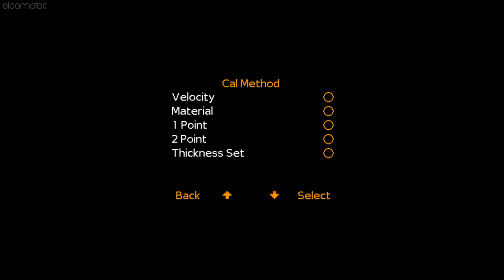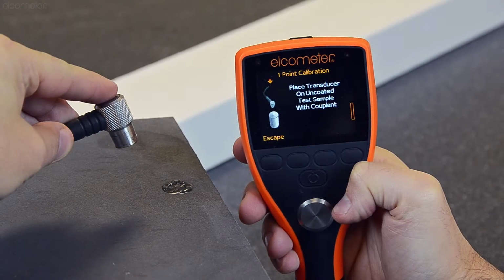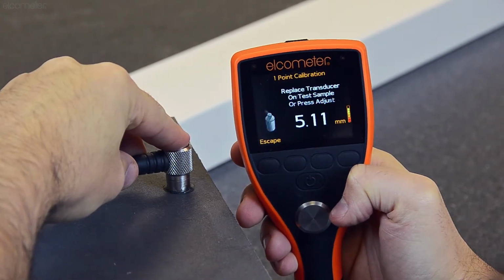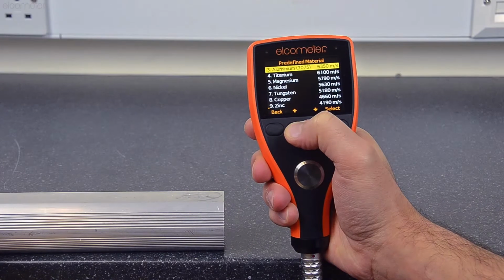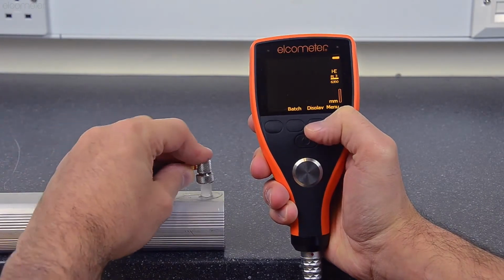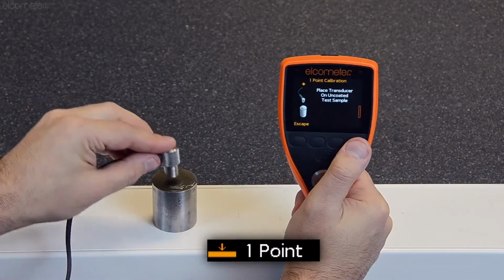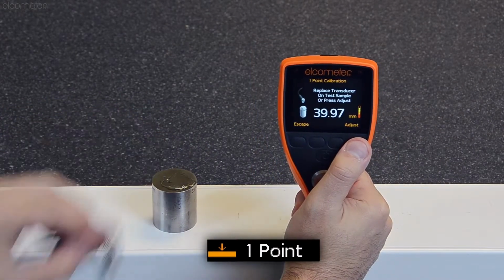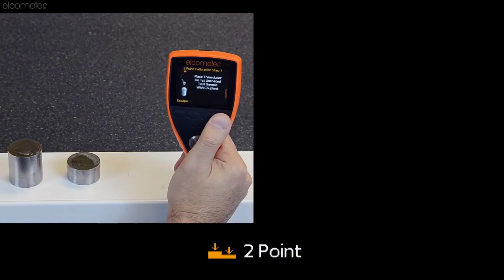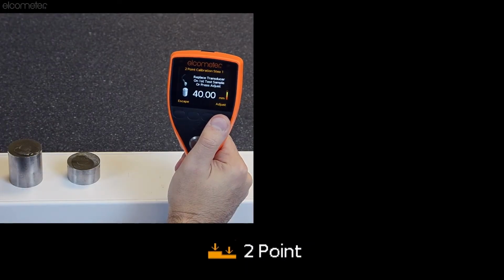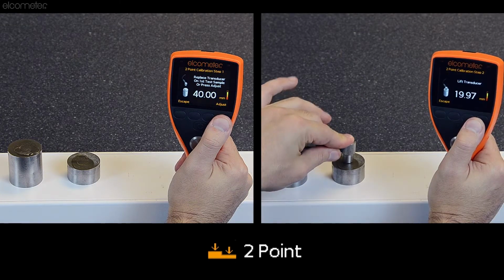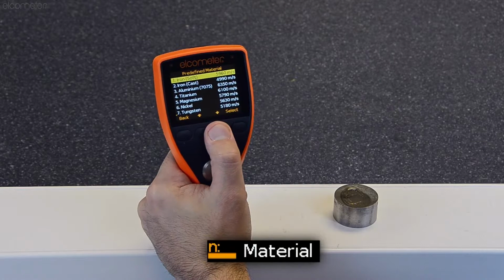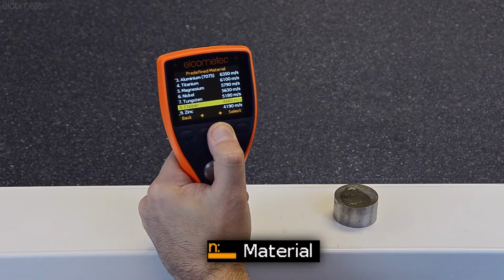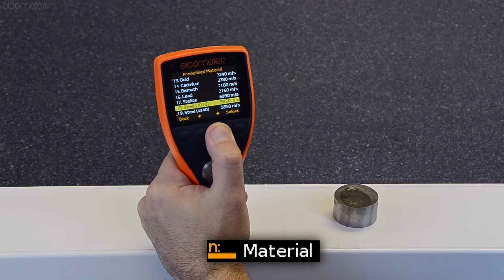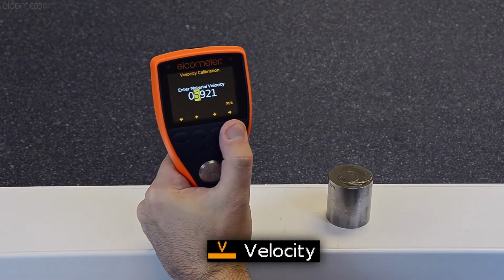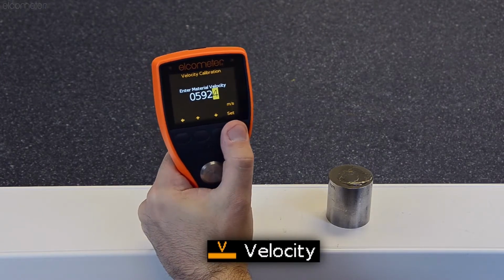The Elcometer 304 and 307 have a range of calibration options, with simple, on-screen instructions that guide you through each method, so it's easy to maintain the gauge's accuracy at all times. The calibration methods include one-point calibration, which uses an uncoated sample of test material of a known thickness, two-point calibration, which uses two uncoated samples of test material of two different and known thicknesses, material calibration, which uses the sound velocity of a material selected from a predefined list within the gauge, and velocity calibration, which uses the known sound velocity of the material under test.